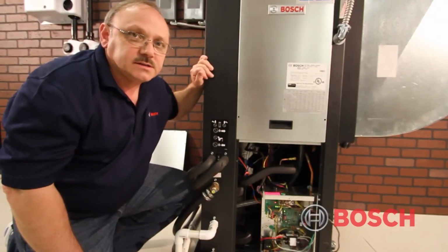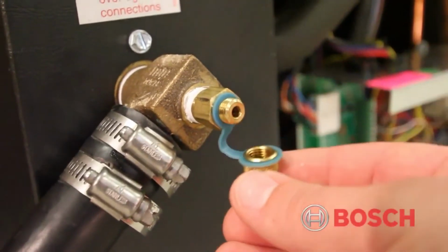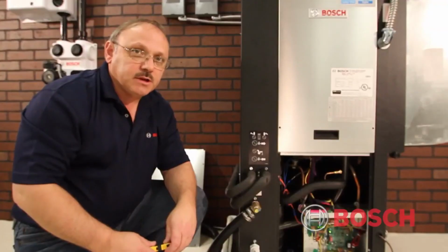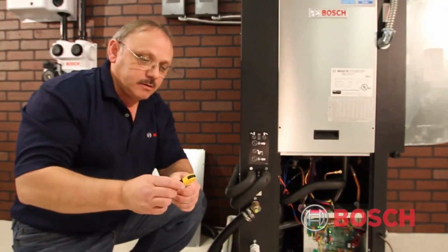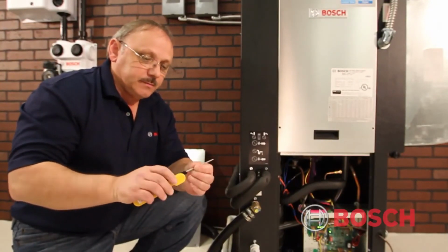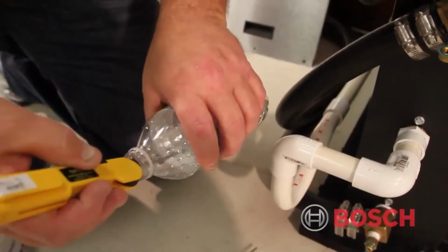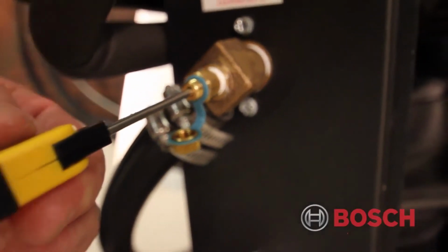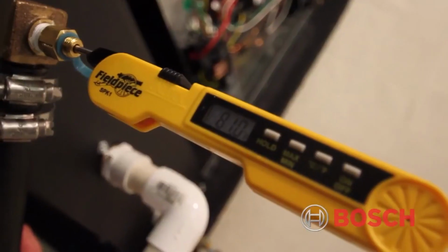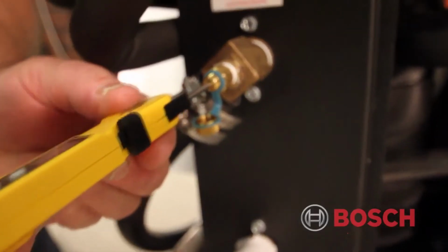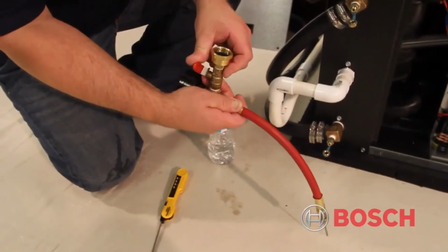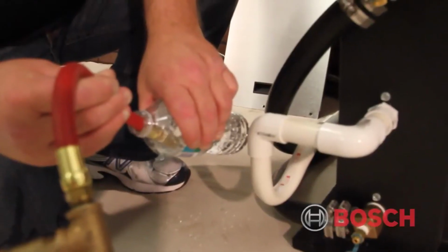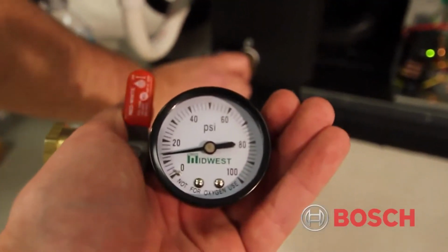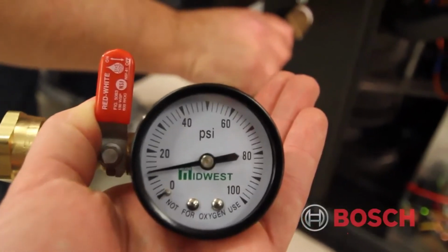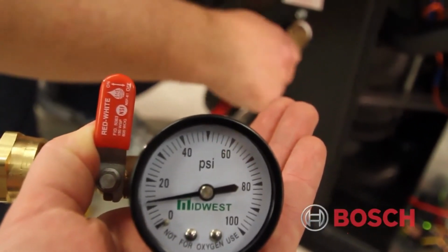Okay, with the unit operating, the first thing we'll do is remove the caps from the PT plugs. We'll take an insertion type thermometer and insert it into the PT ports once we've lubricated the stem on the thermometer, and take a temperature measurement of the water entering the coax and the water leaving the coax. Then we'll remove the thermometer and take our pressure gauge. We'll take the PT port adapter on the pressure gauge, and we'll also lubricate that. We'll take a pressure measurement entering the coax and a pressure measurement leaving the coax, to get our pressure drop, or delta P, to input into our formula.